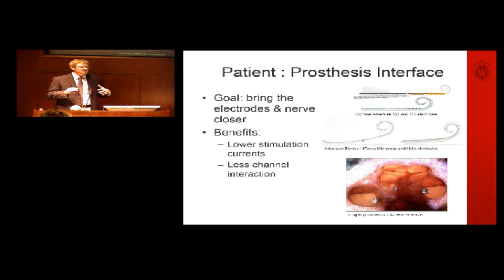And the idea here is that as opposed to having an electrode that's found out here at the lateral or outer portion of the cochlea, this being the hearing nerve, the electrode is really in quite close proximity. The benefit of this is that you can use lower electrical currents to stimulate the nerve. The idea being that if you have to use a larger electrical current, there's more chance that current will spread and it will degrade the speech capacities that the device is able to give, because there's information crossing over into different processing channels.